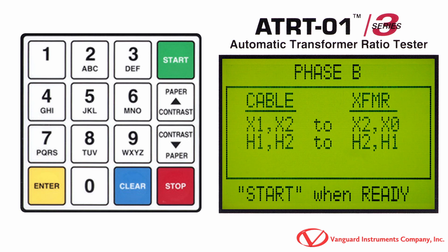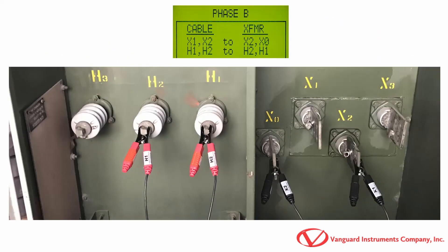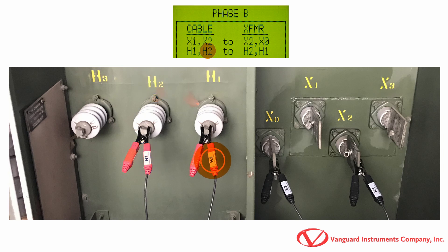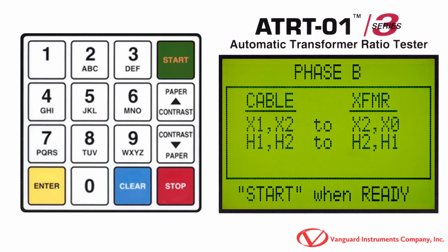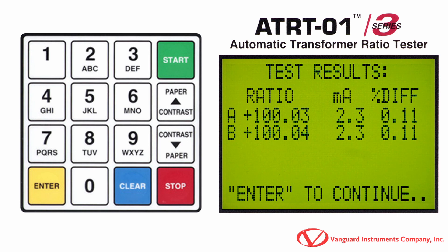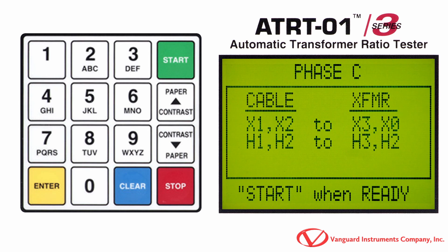Now we'll follow the on-screen instructions to make connections for testing phase B. We'll connect the unit's X1 cable to the transformer's X2 terminal and the unit's X2 cable to the transformer's X0 terminal. Then we'll connect the unit's H1 cable to the transformer's H2 terminal and the unit's H2 cable to the transformer's H1 terminal. Now press the Start key to perform the test. After a few seconds, the test results for phase B will be displayed below the phase A results. Press the Enter key to continue.